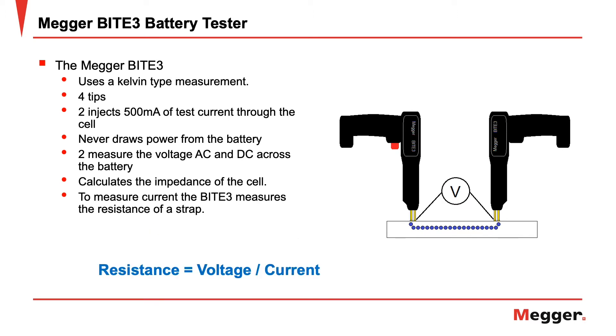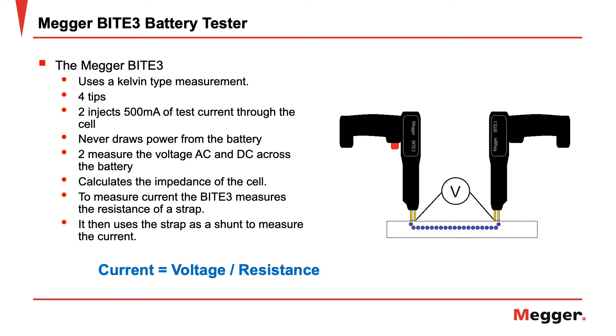When measuring float and ripple current, the BITE3 first measures the resistance of the intercell connection, or the strap. It then uses the strap as a shunt and measures the AC and DC voltage across it. It can then calculate both the AC ripple current and the DC float current, so there's no need for an external CT.